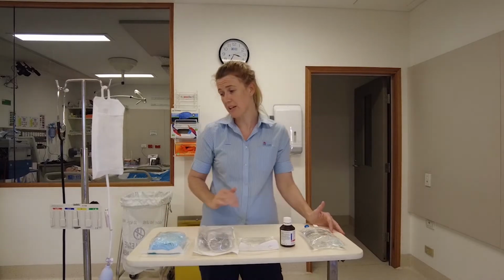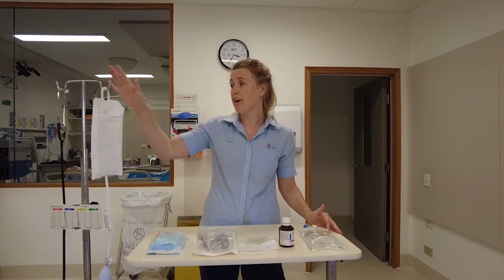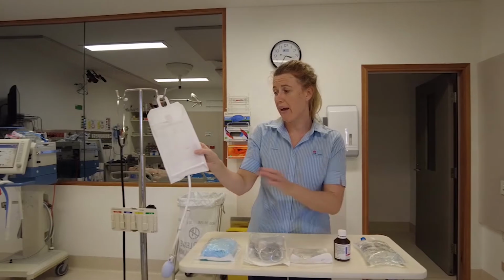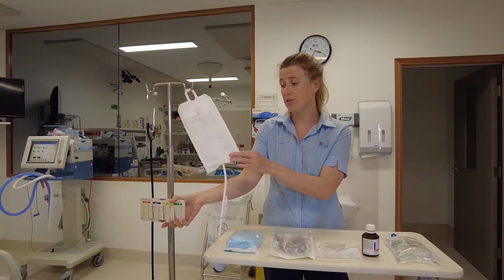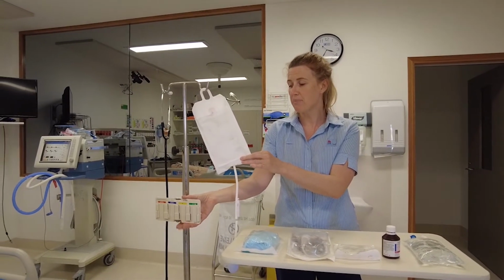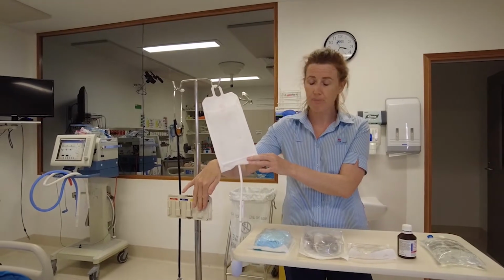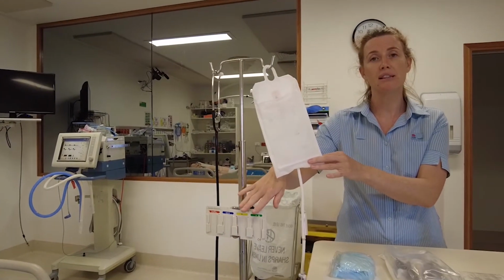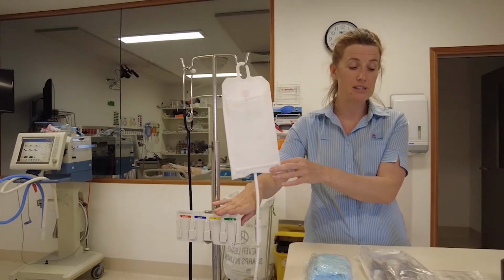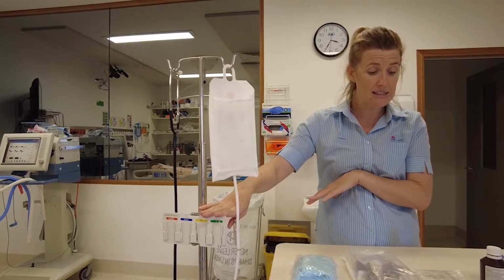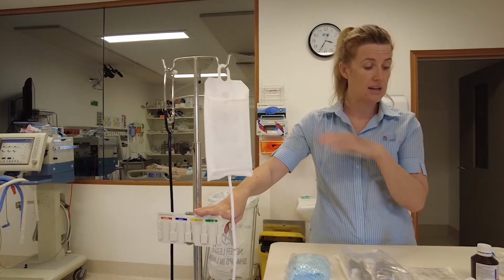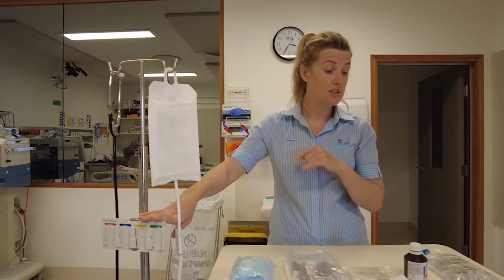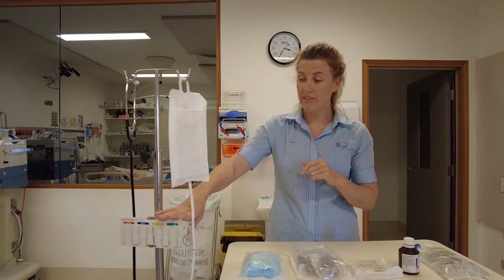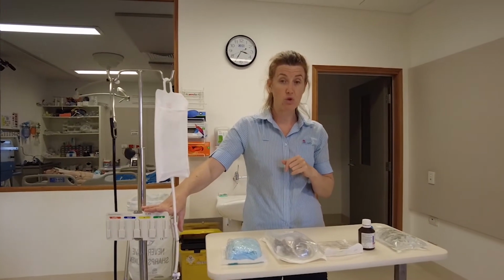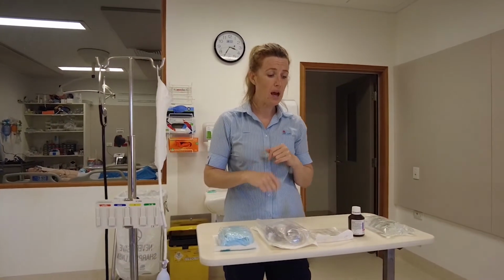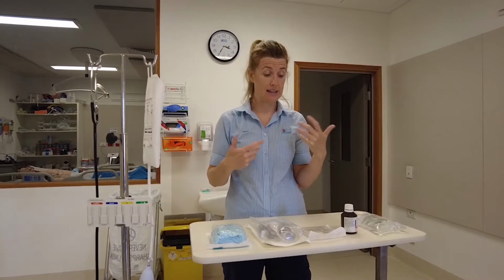All right, so the first thing I've done here is I've gathered my equipment. I have an IV pole, I have a pressure bag, and I have the arterial transducer holder. So this is the bit where we actually put the transducer component, and we're going to move this up and down the pole to level it to the appropriate area. For most of our patients, that's going to be the phlebostatic axis. For some of our patients, it's going to be the tragus or the external auditory meatus. That's usually only in the event of a traumatic brain injury, where we're monitoring and targeting a CPP or a cerebral perfusion pressure.